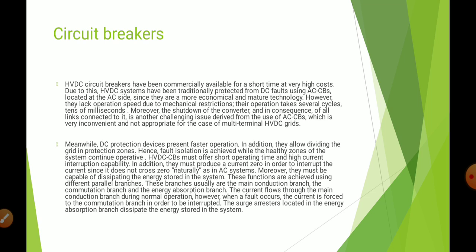Meanwhile, DC protection devices present faster operation. In addition, they allow dividing the grid into protection zones. Like if we have a grid, we can divide it into 3 parts. Hence, fault isolation is achieved while the healthy zones of the system continue operative. Let us assume there is a fault between parts 1 and 3. We can just remove the faulty zone alone and use both healthy zones.